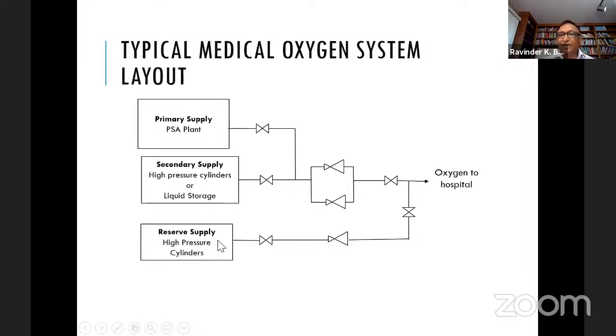A reserve supply can never be liquid, because you're not going to use it, it just sits there until a major emergency. Liquid storage is not good for that, because it doesn't hold oxygen indefinitely. If you don't use it for some time, you end up losing it and there would be nothing available. That's the major difference.